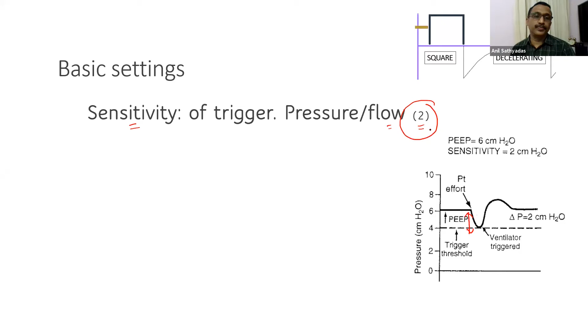So how much drop should be there from the baseline? Normally we keep 2 centimeters of water drop to trigger the ventilator. That means the ventilator will understand the patient is taking a breath and it will give full support to that breath in a volume control mode. It could also be a flow trigger. Again, the value is 2 liters per minute. Just remember the value 2. When you set the trigger, you can set it as 2.